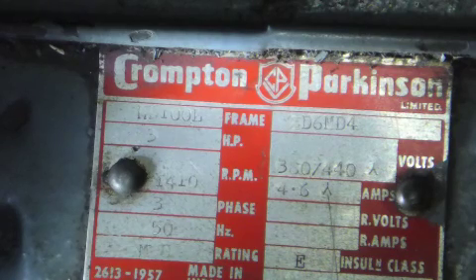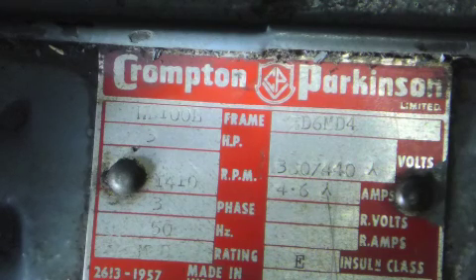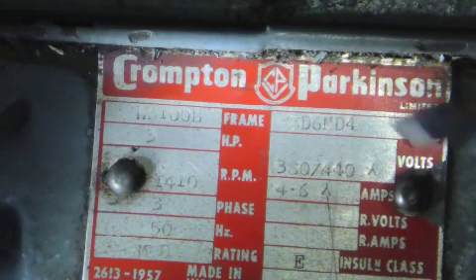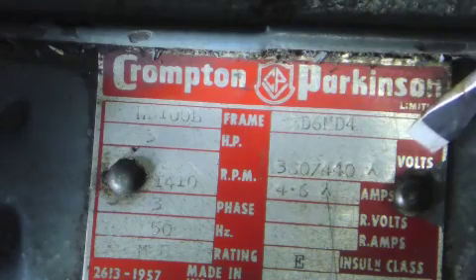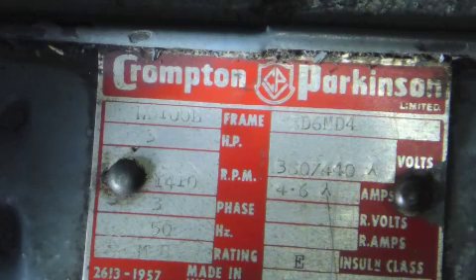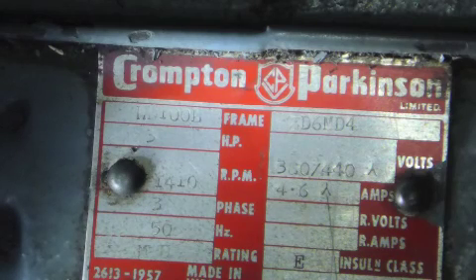So how do you know if you've got a dual voltage motor? This is the motor on my shaping machine as you can see it's reasonably new motor it's externally finned unlike many of the older motors that have a smooth casing. Might be able to make out on there the field which says voltage is marked at 380 to 440. This doesn't mean it's a dual voltage motor that means that is the operating range at which this motor is designed for.